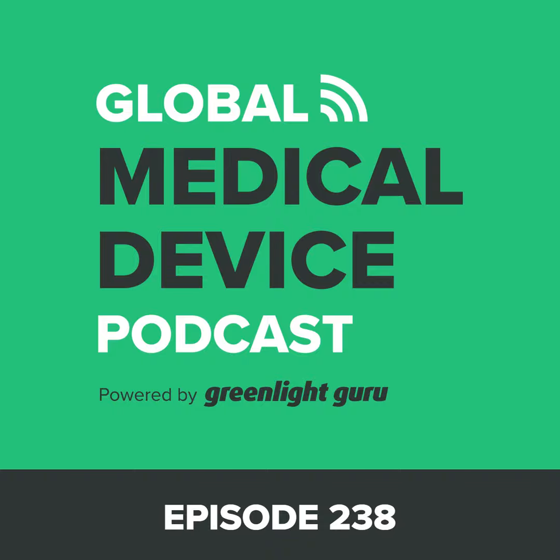But for companies that are working in this clinical decision support software, you have to realize, and I've said this to many of the companies that I've worked with in this space, you have to be prepared for that to change at some point in the future. In other words, FDA is saying that we are not going to regulate these products for now. And so, yeah, you can go ahead and put out one of these software programs, but be prepared. I'm not saying that it will happen, but it might happen. And I'm not saying when it will happen, but it could happen that FDA changes their mind and says, we are now going to regulate these things. And you might need maybe even a 510(k) or a de novo to be able to continue.